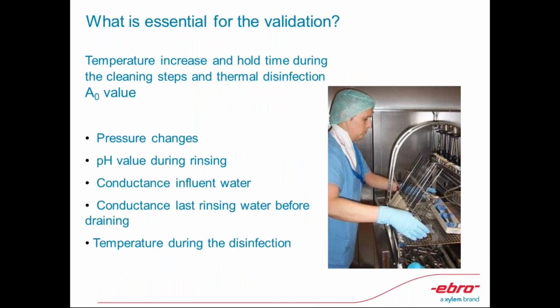So we go to essentials for validation. Now we need pressure, measurements for pressure changes and its behavior during the process. We need pH value during rinsing - it's important but optional. We need specific conductance in influent water, specific conductance in the last rinsing water, and temperatures during the disinfection.